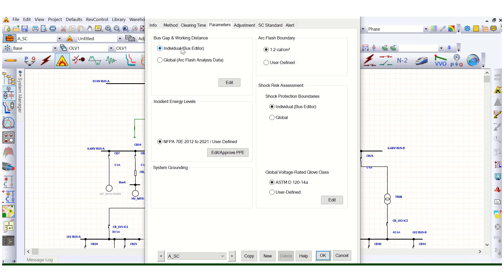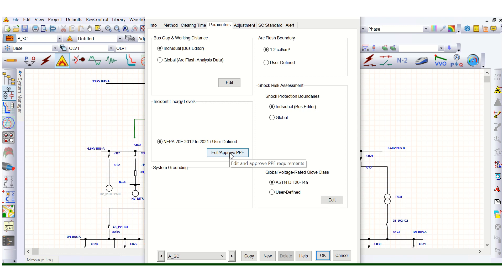Go to the parameters tab. Here you configure bus gap, working distance, and other individual settings. The Arc Flash boundary is important — it can be user defined, and by default it is 1.2 calories per centimeter squared incident energy level. The incident energy level is as per NFPA 70E 2012 to 2021.